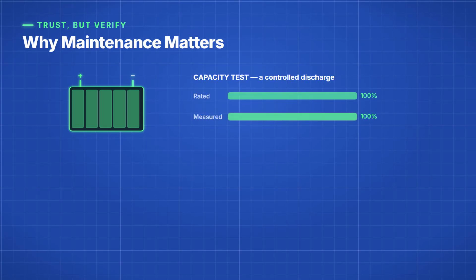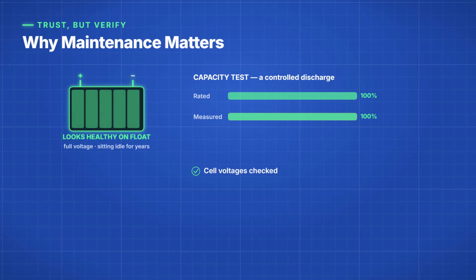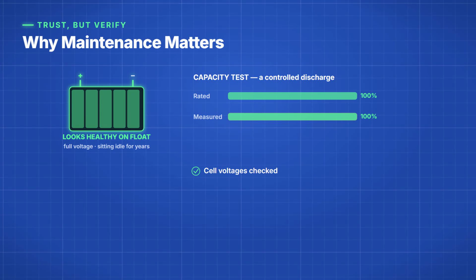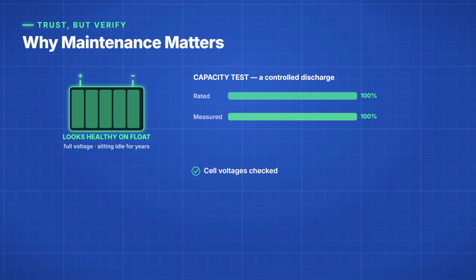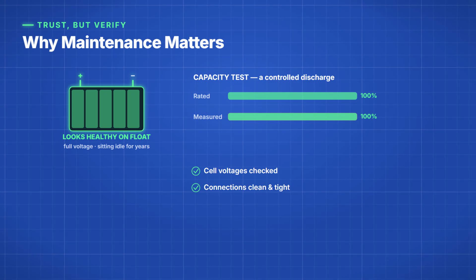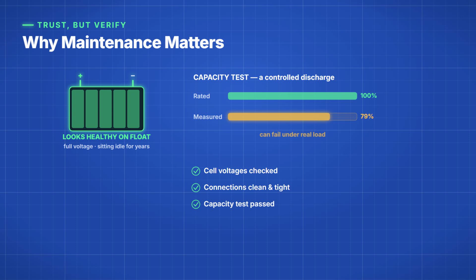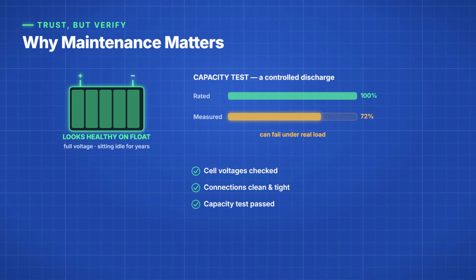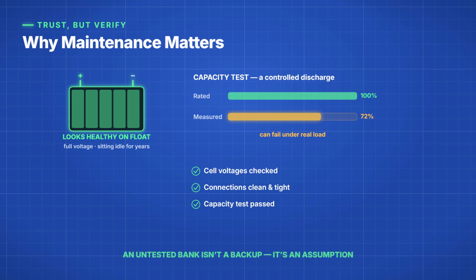A battery can sit on float for years looking perfectly healthy and still fail to hold up under load when it finally has to. That's why maintenance is taken so seriously. The voltage of each cell is checked and the connections are kept clean and tight. And every so often, the whole bank is given a capacity test. That's a controlled discharge that proves it can still do its job. A battery bank you haven't tested isn't really a backup, it's an assumption.